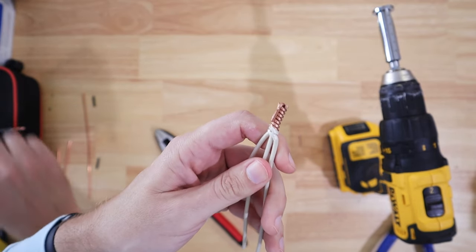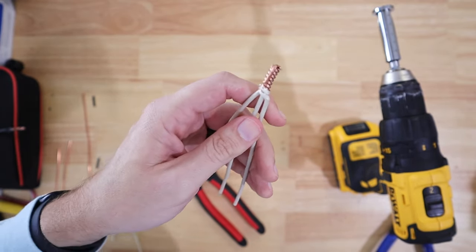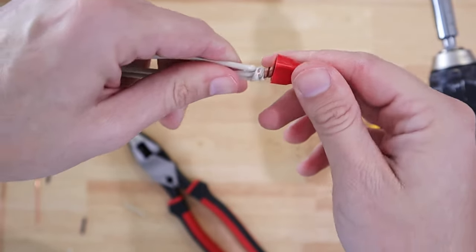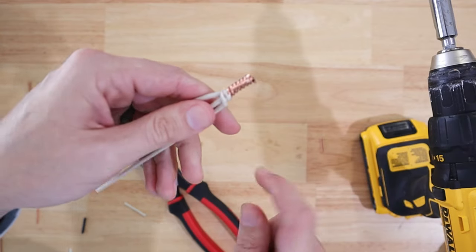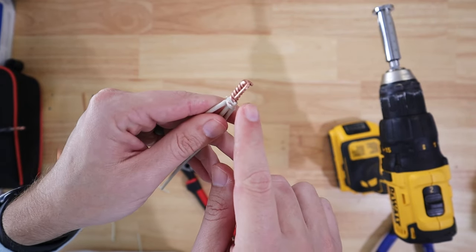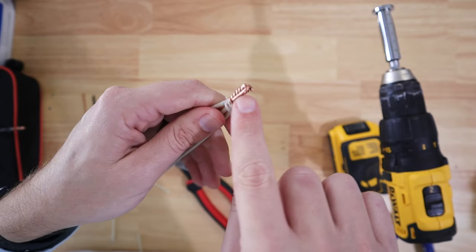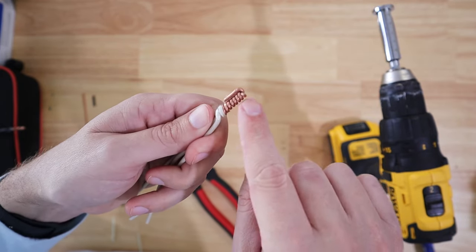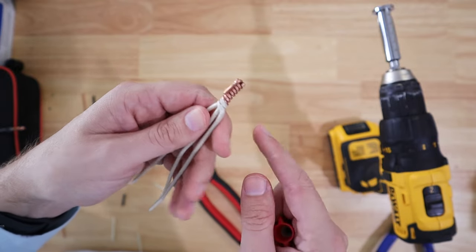However, what I don't like about this is when I go to put my wire nut on, this is way too big. I'd have to use a massive wire nut. And even if I do get a wire nut on top of this, it's not going to be connecting with any of the wiring that's underneath of this piece of metal that I basically flap down. It's just going to make connections on this side and then on the center piece of wire that got folded down.